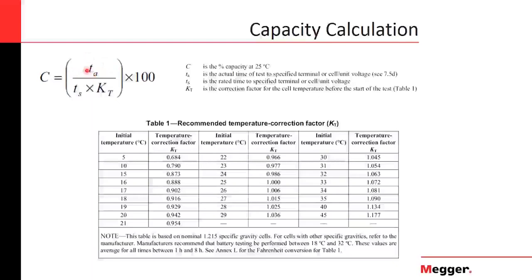As best practices, well, you want to run the test for a time as close as possible to the duty cycle of your battery, of your substation. This will give you the confirmation of the capacity, and also will tell you if the battery is capable of meeting the duty cycle of the substation without running a performance test or a modified performance test, which might be a little bit complicated. For trending purposes, try to always use the same duration.